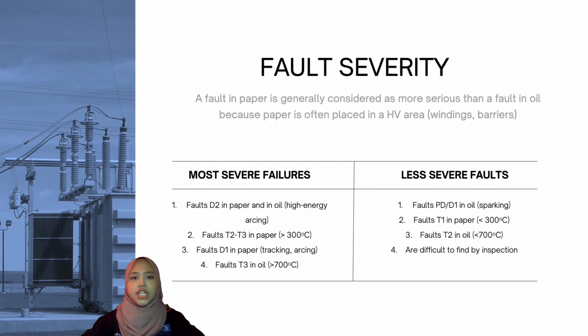For fault severity, a fault in paper is generally considered more serious than a fault in oil because paper is often placed in a high voltage area. For the most severe failures, first, faults D2 in paper and in oil, high energy arcing. Second, faults T2 or T3 in paper, greater than 300 degrees Celsius. Third, faults D1 in paper, tracking or arcing. Lastly, faults T3 in oil, greater than 700 degrees Celsius.